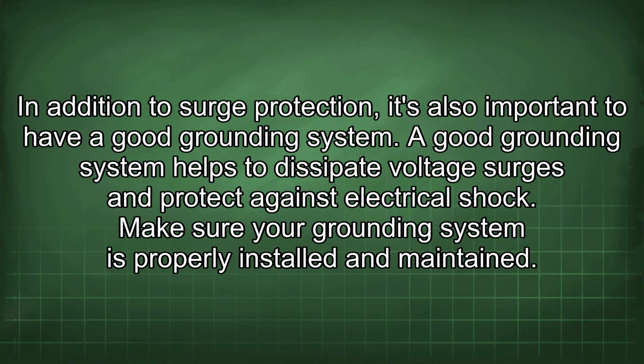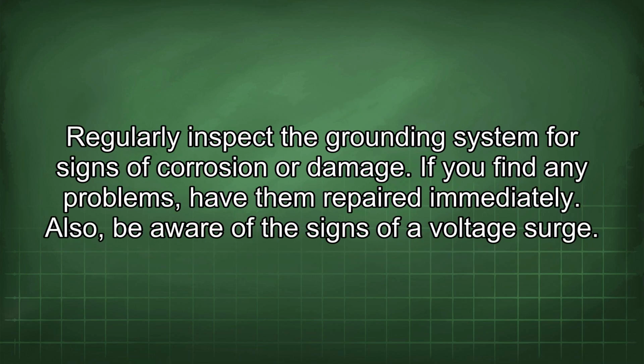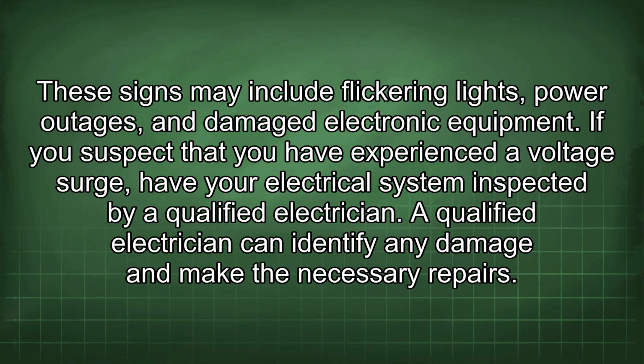In addition to surge protection, it's also important to have a good grounding system. A good grounding system helps to dissipate voltage surges and protect against electrical shock. Make sure your grounding system is properly installed and maintained. Regularly inspect the grounding system for signs of corrosion or damage. If you find any problems, have them repaired immediately. Also, be aware of the signs of a voltage surge. These signs may include flickering lights, power outages, and damaged electronic equipment. If you suspect that you have experienced a voltage surge, have your electrical system inspected by a qualified electrician. A qualified electrician can identify any damage and make the necessary repairs.